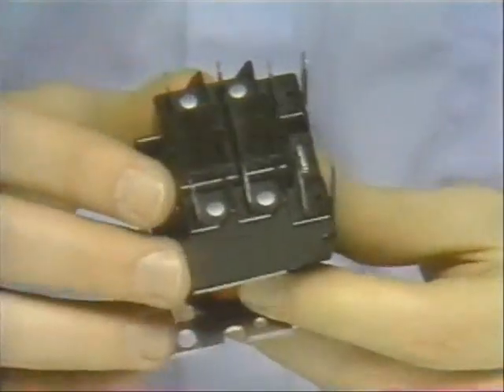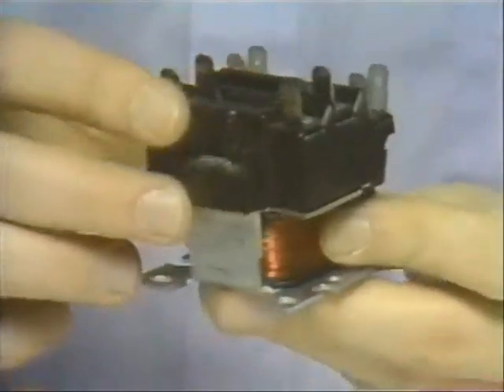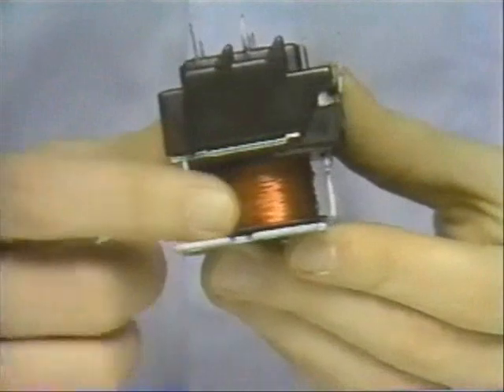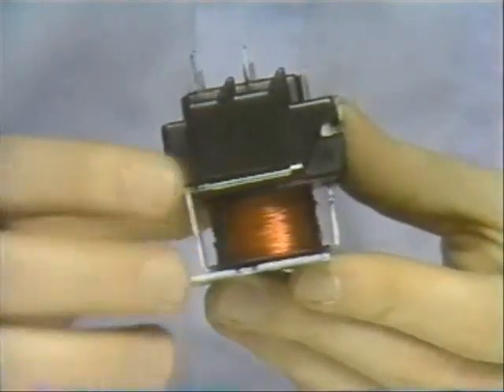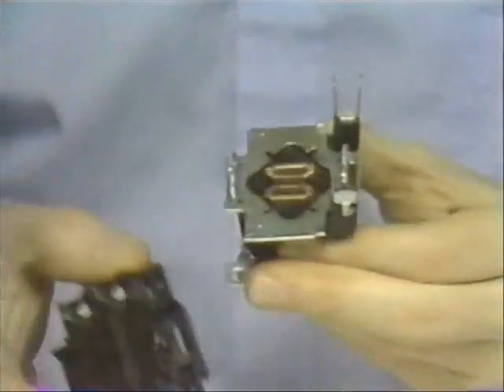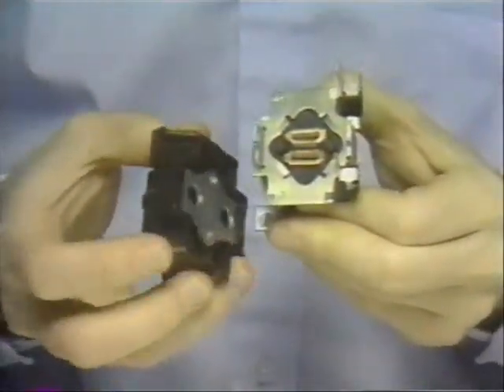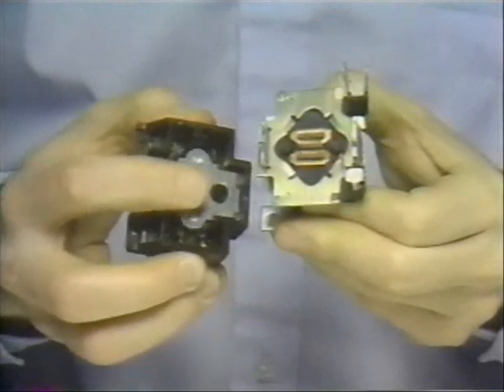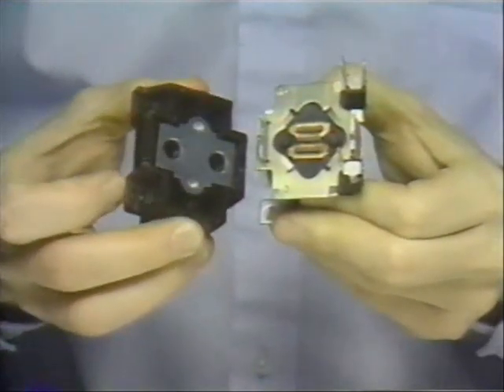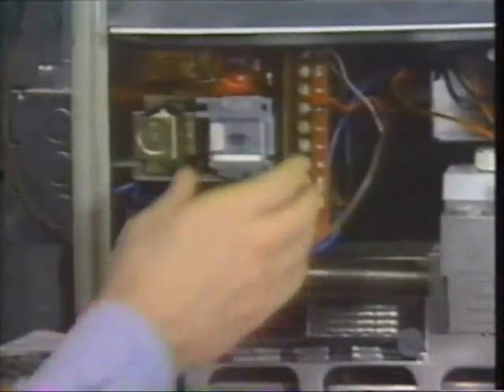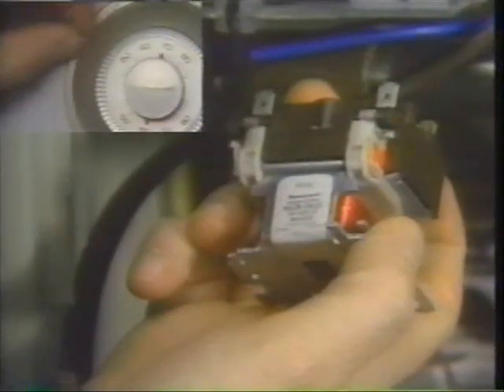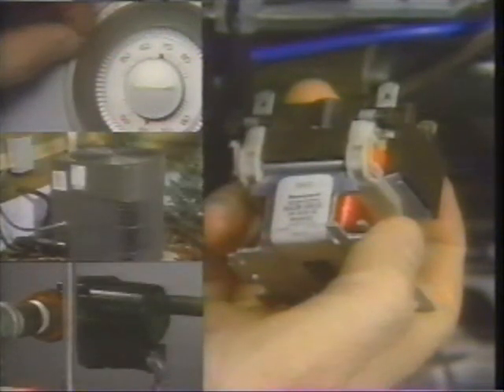A coil is wrapped around a magnetic core. When current flows, the core becomes magnetized and attracts an armature, closing the relay's contacts and turning on the power in one or more circuits. When current to the coil is shut off, springs return the armature and contacts to their original positions, turning off the power in other circuits. One key feature of a relay is that very little current is needed to energize the coil and switch the contacts. As a result, a small switch, like a low-voltage thermostat, can be used to switch line voltage circuits and control fans, compressors, and other equipment.